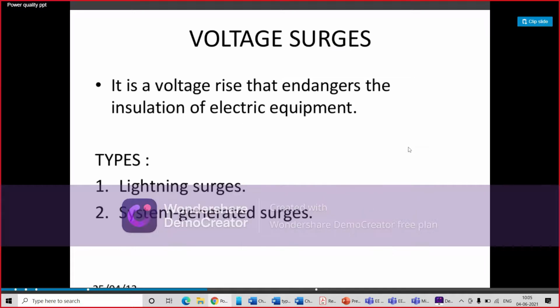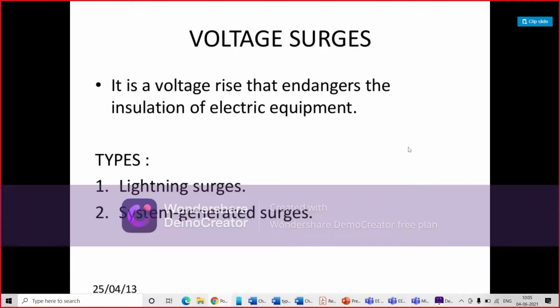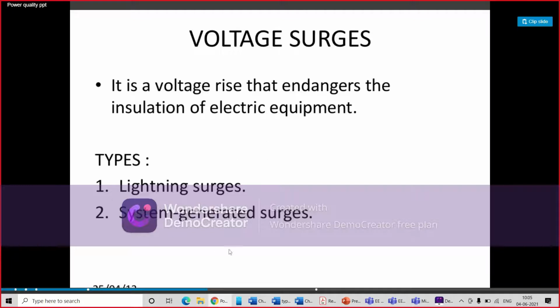Okay. Then you have this voltage surge. It is basically a voltage rise that endangers the insulation of the electric equipment. So it could be of two types: lightning surge and system generated surges. What are the causes of these surges? Shutdown of heavily loaded circuits, necessary commutation of a high-powered network, switching events such as connection or disconnection of current, and short circuit to ground. What can they lead to? Computers and other sensitive electronic equipment can be seriously damaged by such an overvoltage surge, and temporal fluctuations produce parity errors and interrupt protection systems.